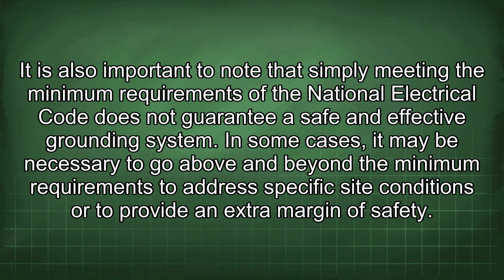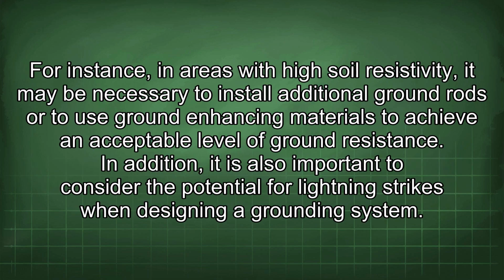In some cases, it may be necessary to go above and beyond the minimum requirements to address specific site conditions or to provide an extra margin of safety. For instance, in areas with high soil resistivity, it may be necessary to install additional ground rods or to use ground-enhancing materials to achieve an acceptable level of ground resistance.